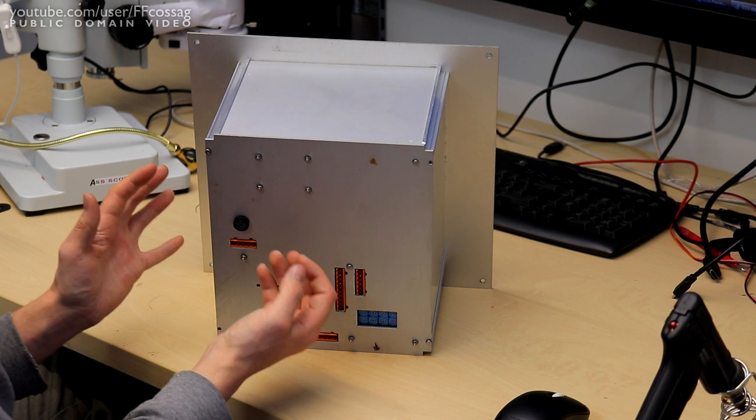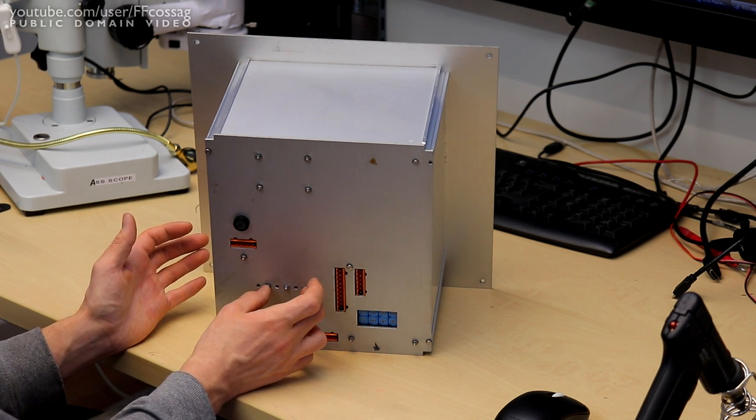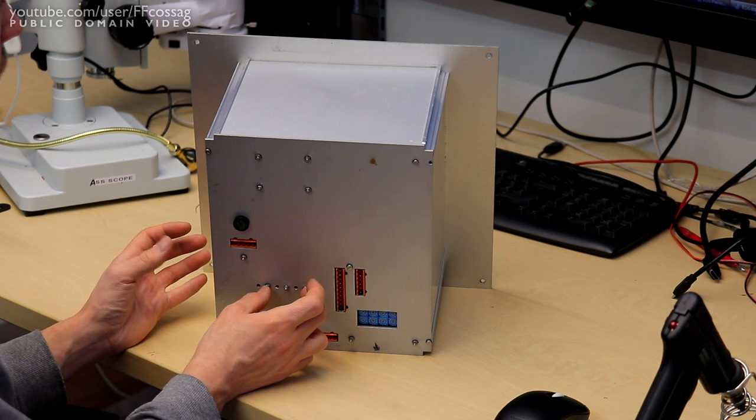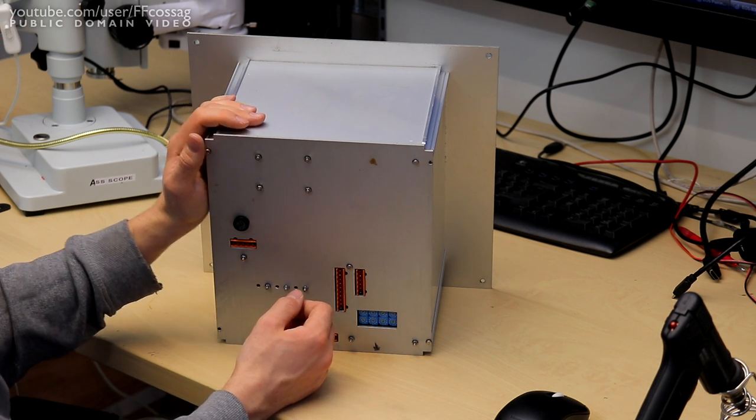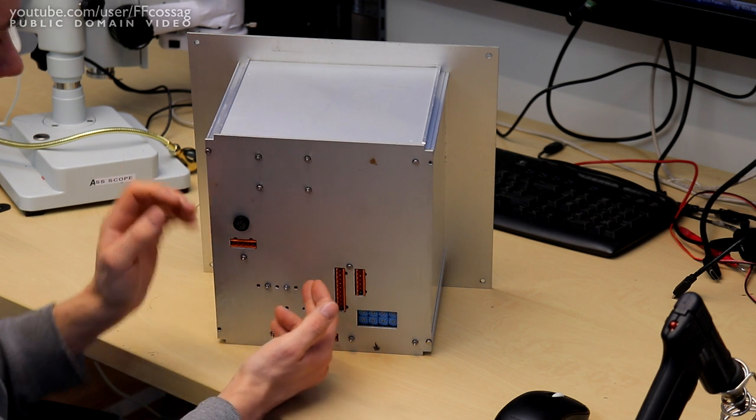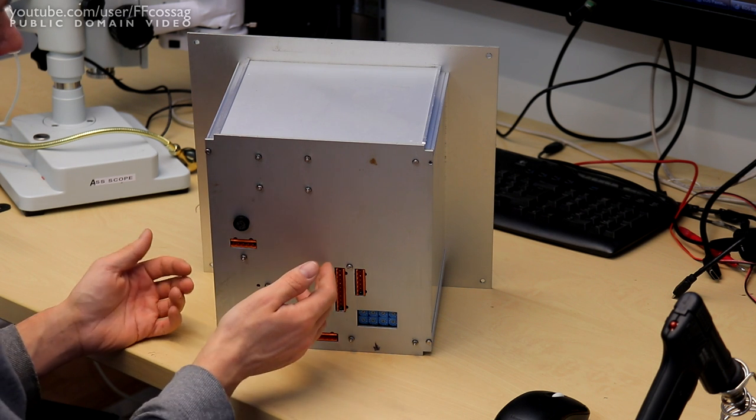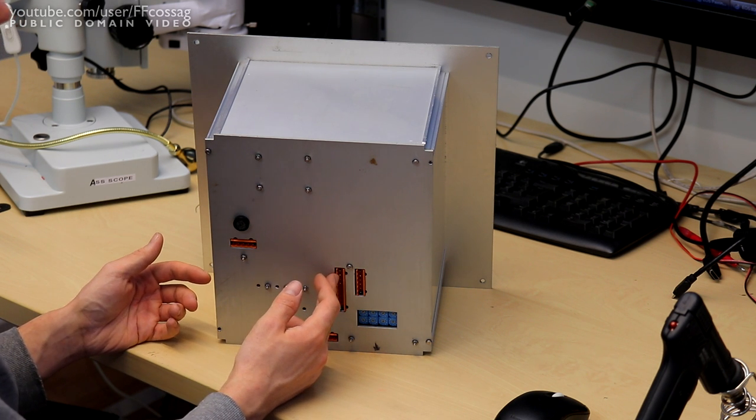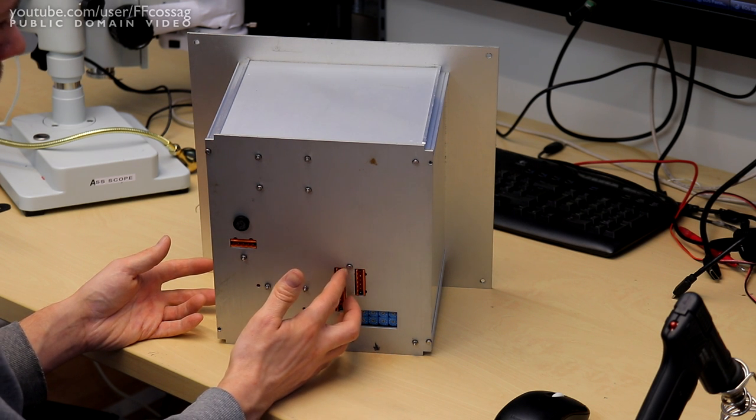The 24 volt was probably there all along, although we can't know for certain. What we do know is the 24 volt is there right now and it's still blind on the input. I've been to the site where this is installed, we've checked the limit switch that it can't see. While the switch is dodgy, kind of high resistance-ish, the output does go proper low, and it won't respond even if we short the two sensor pins together.